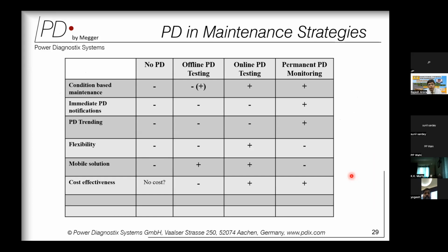Now, if we talk about the partial discharge phenomenon, we know how PD occurs, why PD occurs, and what kind of PD occurs. So let's see how you can measure partial discharge in GIS. In GIS, the partial discharge strategies could be: first, no PD, you don't do any measurement, you are relaxed, you are not exposed. Then you do offline PD testing, that is a commissioning test, meaning when the GIS is not charged.